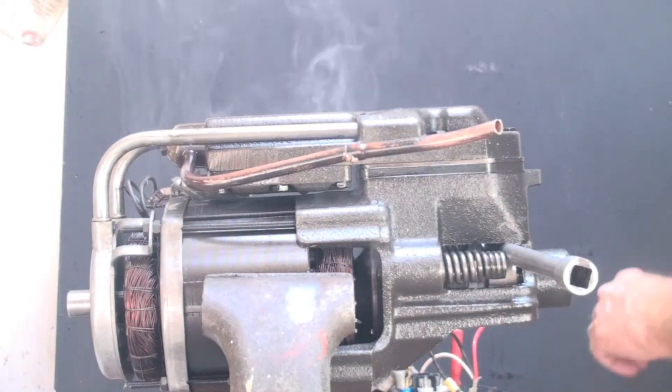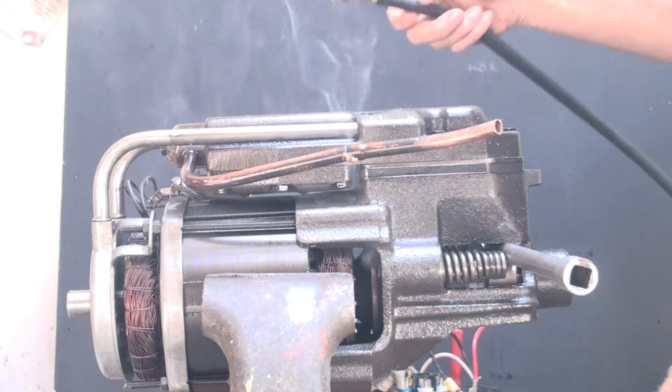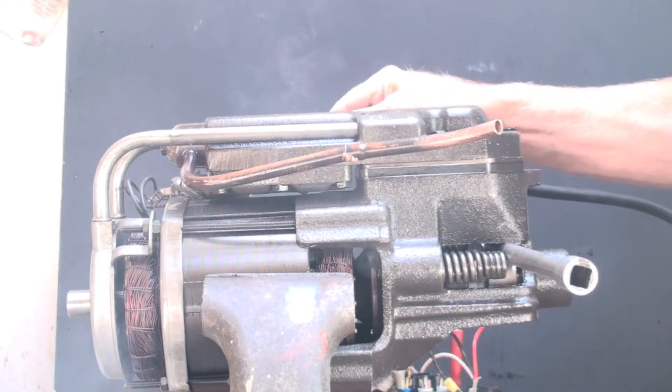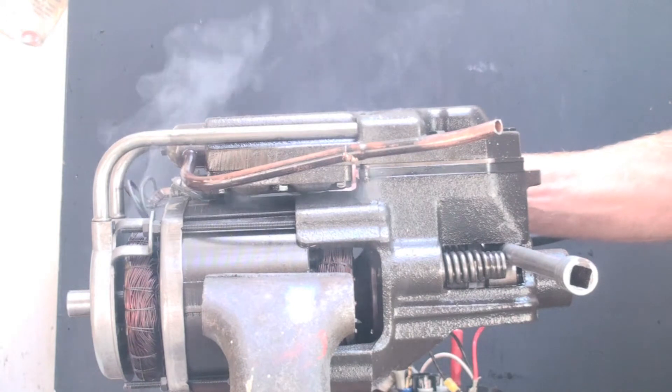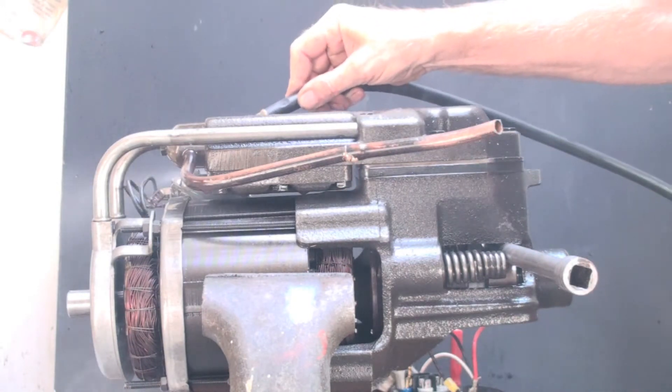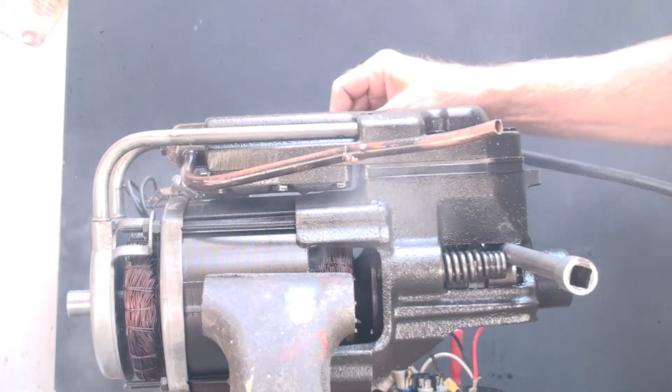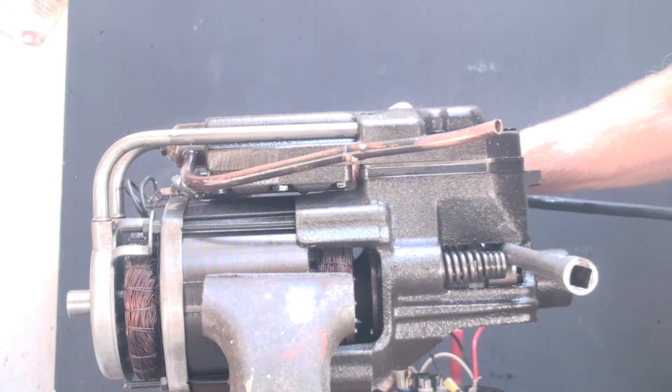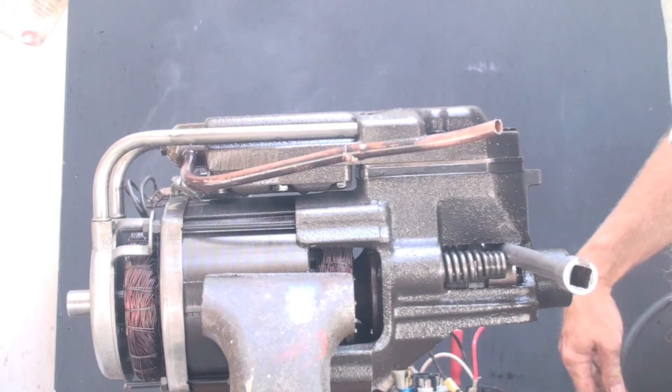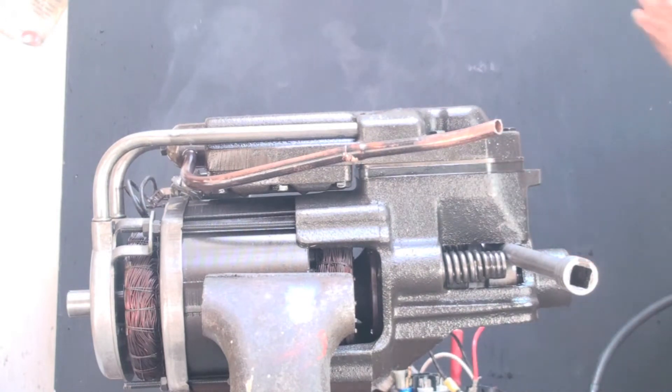Okay, in this one we're going to test this compressor to failure. See, I've already warmed it up quite a bit. I'm cooling down the internal overload on the back side of this thing, and we're going to run this thing lock rotor, no start caps, just run cap and start. We're going to keep running this thing until it gives up.